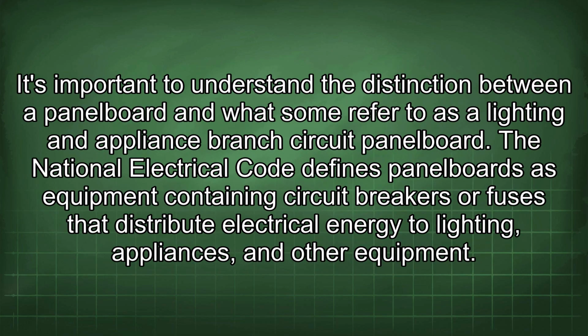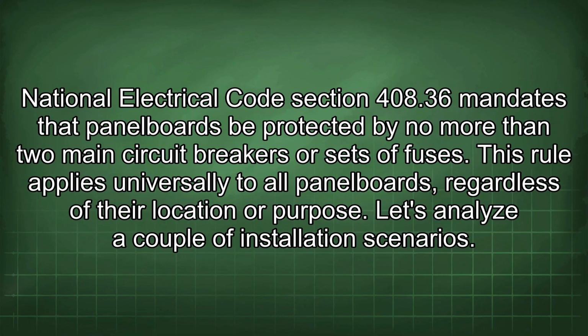It's important to understand the distinction between a panel board and what some refer to as a lighting and appliance branch circuit panel board. The National Electrical Code defines panel boards as equipment containing circuit breakers or fuses that distribute electrical energy to lighting, appliances, and other equipment. National Electrical Code Section 408.36 mandates that panel boards be protected by no more than 2 main circuit breakers or sets of fuses. This rule applies universally to all panel boards, regardless of their location or purpose.